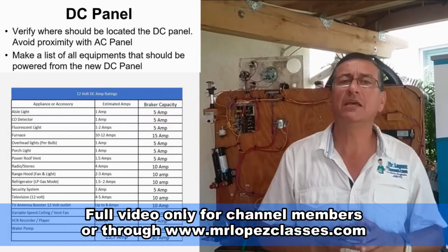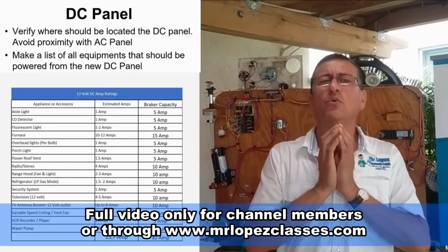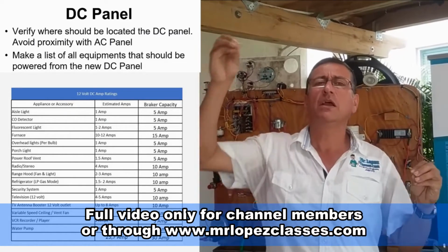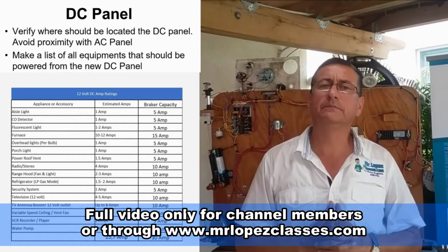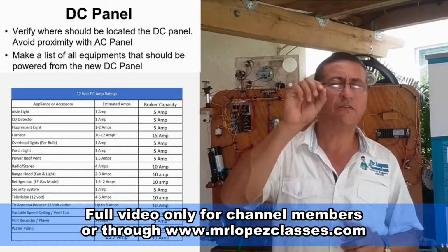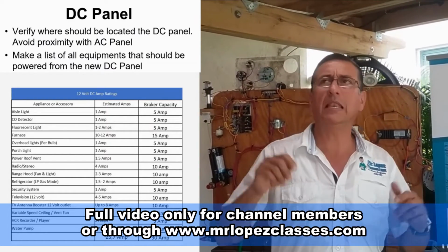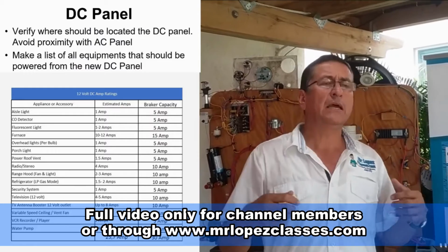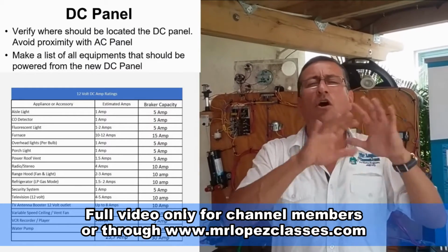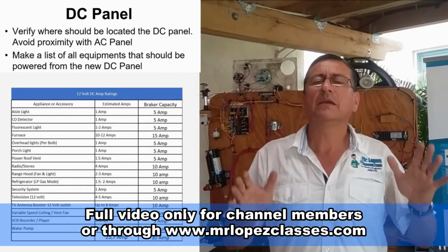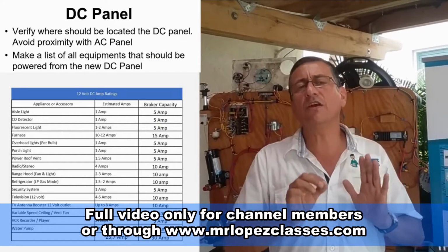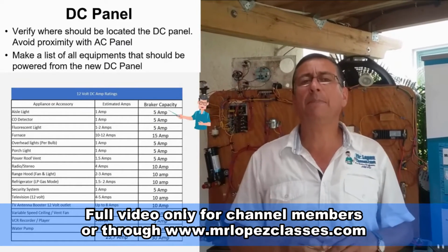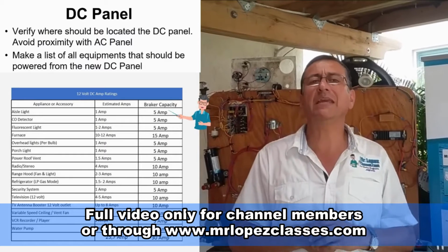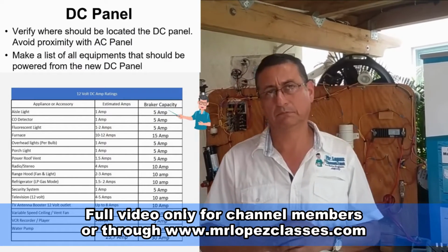Because soon or later you can make a mistake and produce a short. You need to make a list of all the equipment that we are going to connect on the DC panel. For example, I am going to install blowers, lights, and all the DC equipment. You need to make a list and in front of it put the capacity of each equipment in amps per hour.